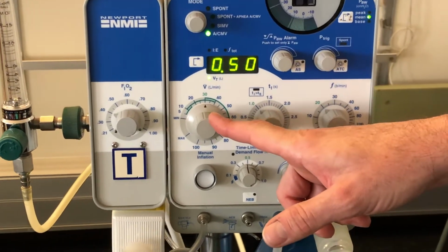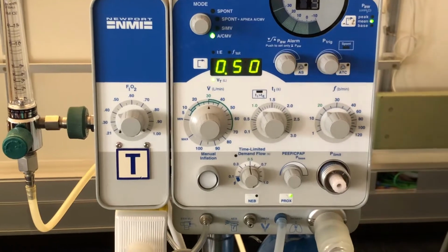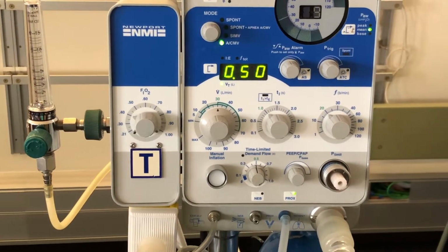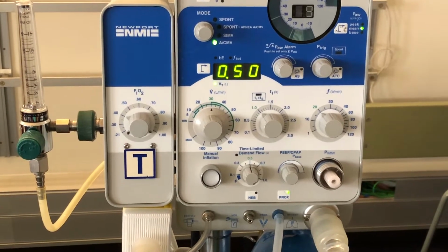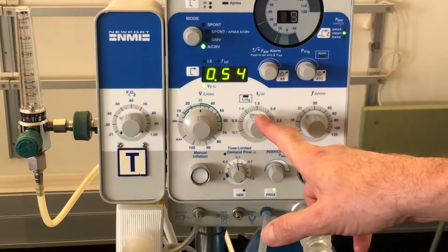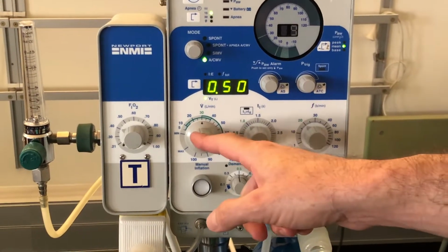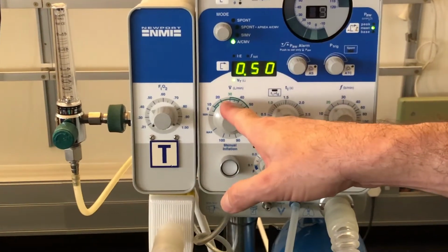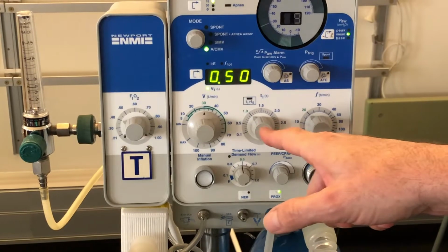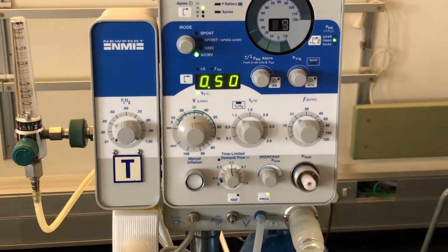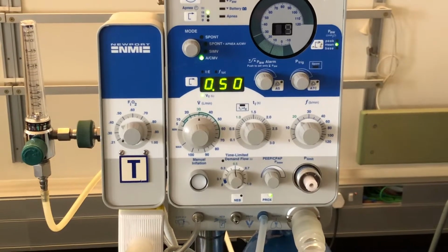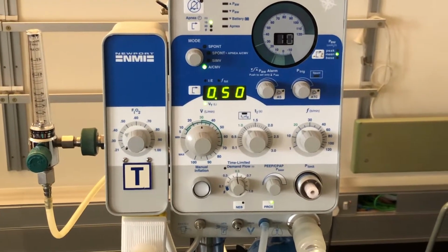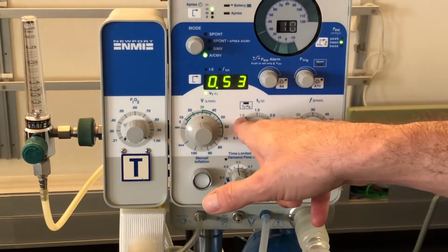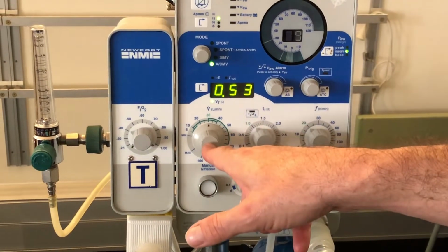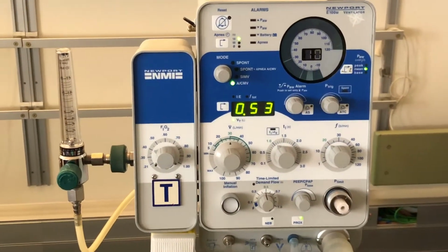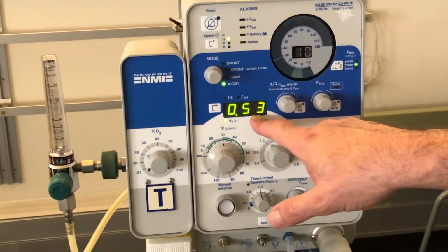The next thing we've got here is the inspiratory flow rate. And it's important then to realize that on this ventilator you don't set a tidal volume directly. Because we've set an inspiratory time and we set an inspiratory flow rate, the machine will deliver the flow rate we set for the amount of time that we've chosen. So if we set the inspiratory flow rate on 30 liters a minute, clearly 30 liters in 60 seconds must be the same as a half a liter per second. Then in the 1 second that we've set as inspiratory time, then the machine should deliver a tidal volume of 500 mils. And we can check that on the panel with the LED display.